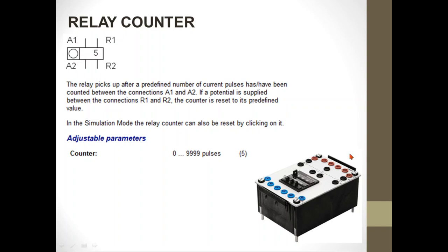After the preset count, the operator can manually press the reset button and the count will reset to zero. After the counter has counted — say, five times — the auxiliary contacts change position. In order for the relay counter to be used again, the preset count must be reset to the starting value, which is zero. Without resetting, the relay counter will not be able to function.